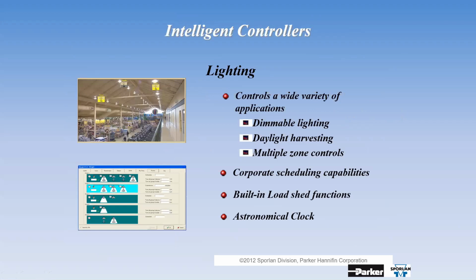For lighting, we use the 508 or 512. We can do dimmable control, daylight harvesting, multiple zones, and all kinds of corporate scheduling capabilities. If your provider requires load shedding, we let you choose: first, all the wall sconces go off; second, we take out all the mood lighting; third level, we get rid of 25% of the aisle lights, and so on. We use an astronomical clock instead of relying on a mechanical clock, so as daylight gets longer or shorter, the clock makes accommodation automatically, and it also knows when to switch for daylight savings time.